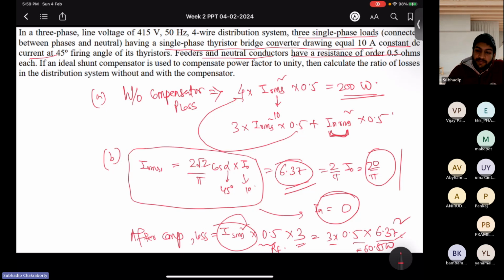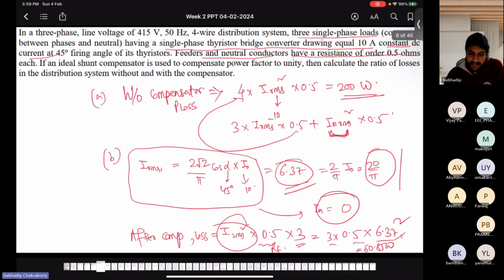So these types of problem you need to tackle first by drawing the waveform. Just check. Don't go by your analysis philosophy that every time ISA plus ISB plus ISC is 0. It is not true. So this matters because you have encountered additional loss in the neutral feeder. So that's why we learned this power quality and to design the compensating tools.